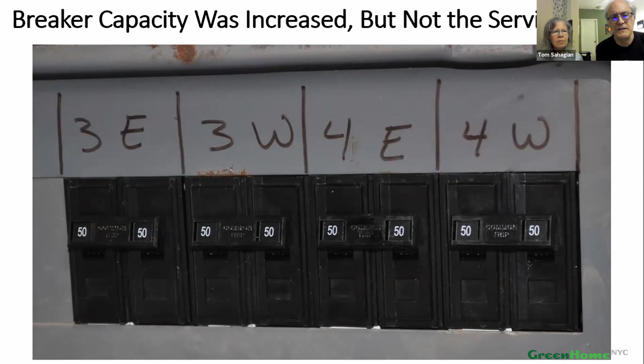So these are 50 amp breakers. We upgraded the breakers to the apartments because the wire size allowed it, going from 40 times 2 to 50 times 2. So we didn't increase the service, but we increased the headroom on the system. I'm pleased to say we haven't popped a breaker in a year, despite very cold and very hot weather.